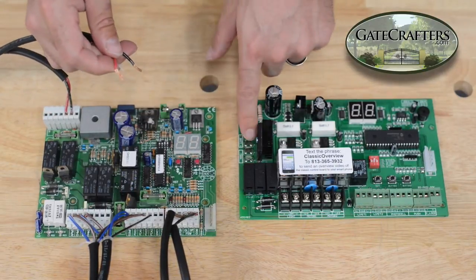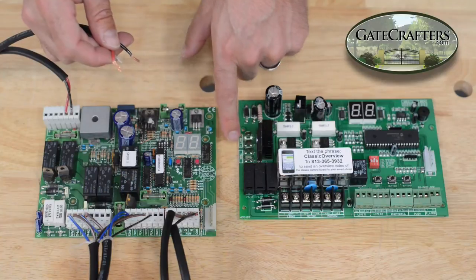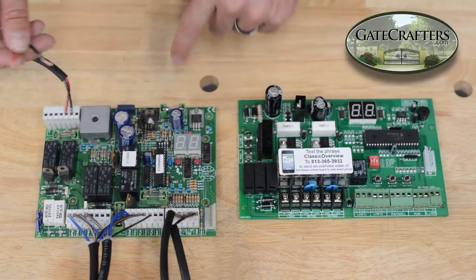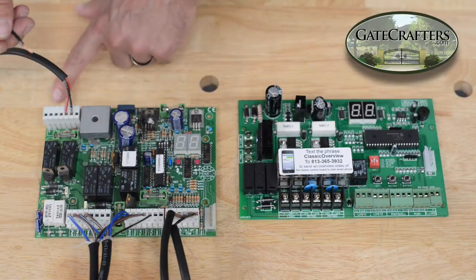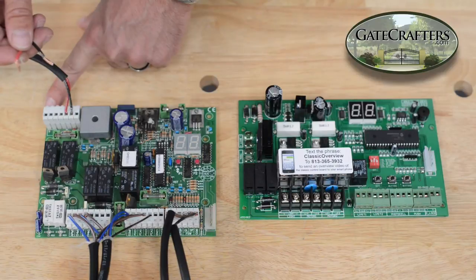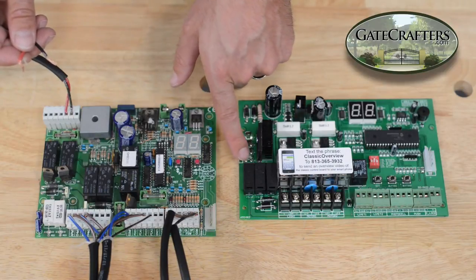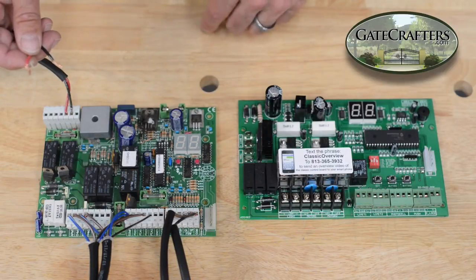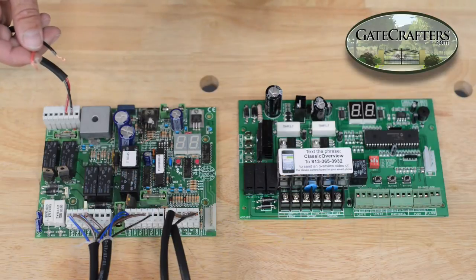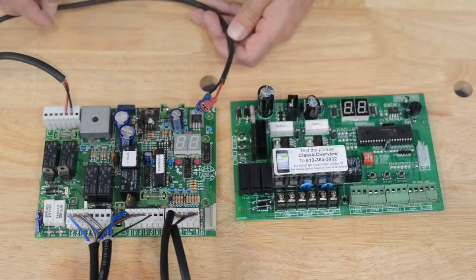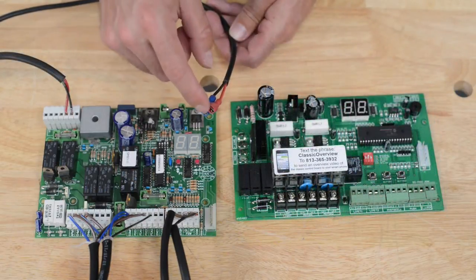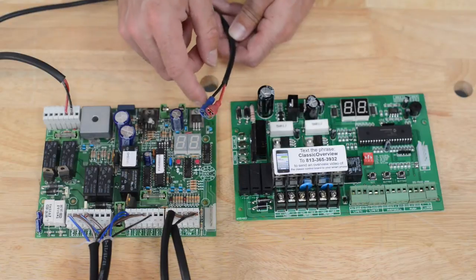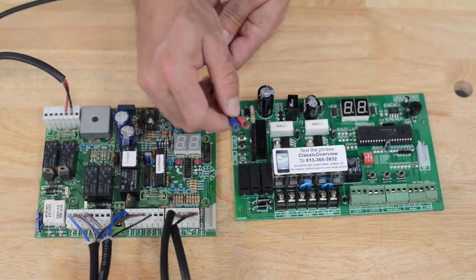We're going to move these over to the TRAN terminals, here and here. Just as with the VAC terminals on this board, there is no polarity on the TRAN terminals. We have to put clips on the end of these, which I'm going to do now. Once we have crimp-on spade connectors, we can now connect these wires to TRAN terminals.